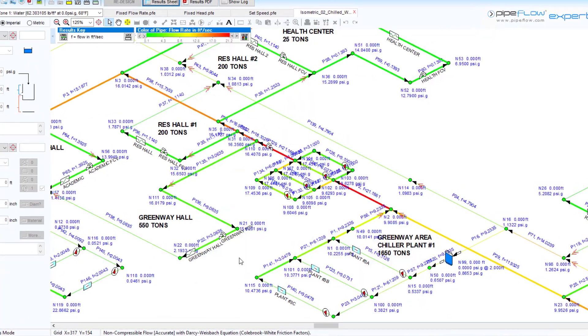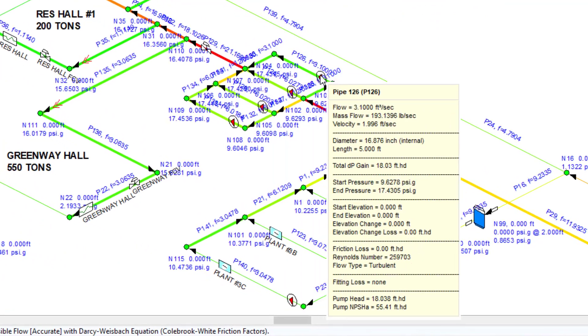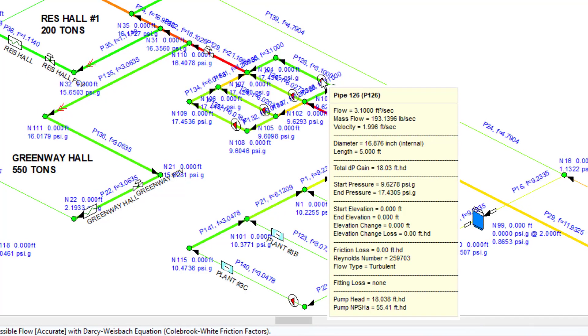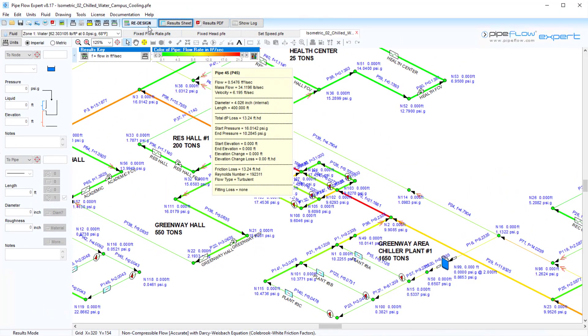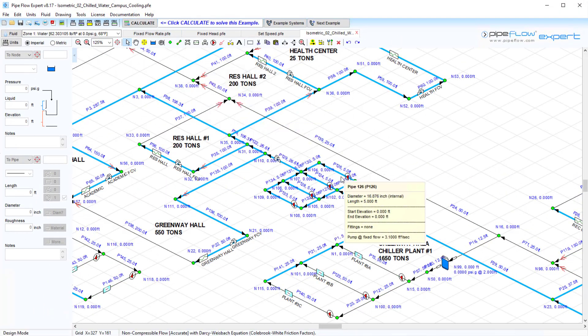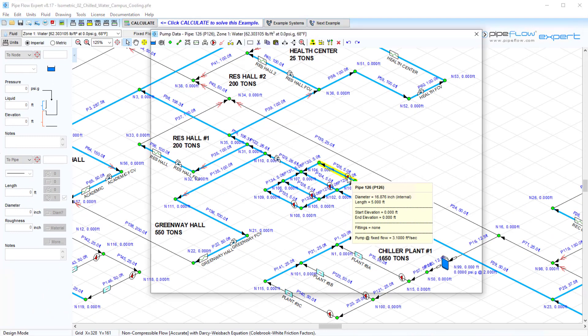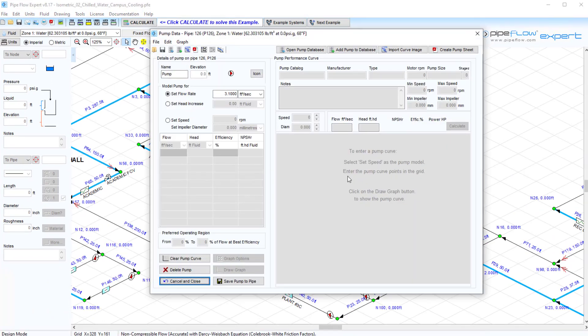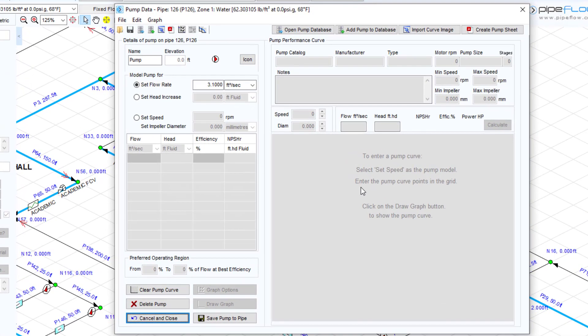Now hovering over the pump we can see that the head increase required by this pump is about 18 feet head. We can then select a centrifugal pump that meets this flow and head requirement from our preferred pump manufacturer or search the generic pump database available within the software.